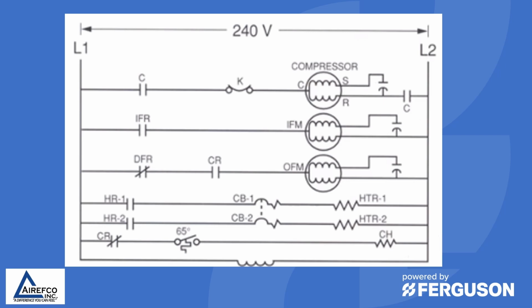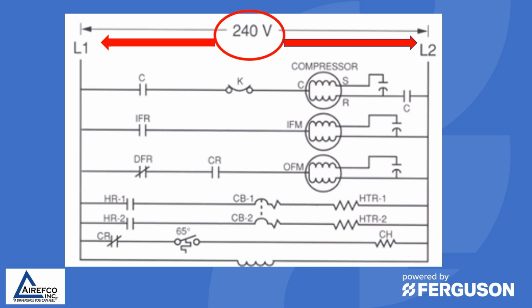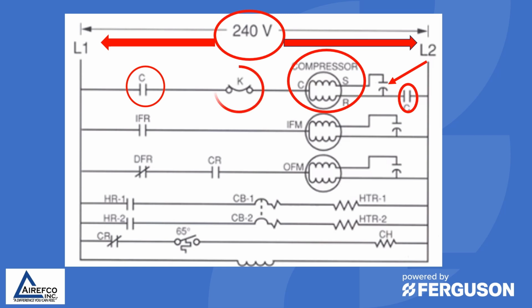In this top view of the 240 volt circuit, we are supplying 240 volts to this system on L1 and L2. We have a compressor with the common start and run windings with a run capacitor, and it is controlled by the contactor contacts, which are in this case normally open. When the contactor is energized, these contacts will close and will bring on the compressor. We also have depicted here a thermal overload that is probably internal to the compressor, a klixon type switch that when the compressor overheats, it will open up and shut down the compressor.